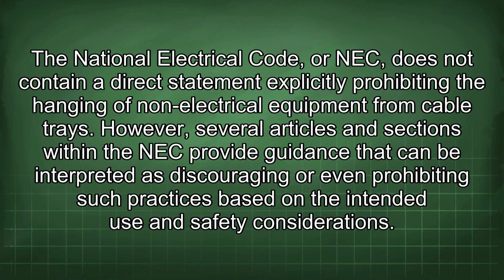The National Electrical Code, or NEC, does not contain a direct statement explicitly prohibiting the hanging of non-electrical equipment from cable trays. However, several articles and sections within the NEC provide guidance that can be interpreted as discouraging or even prohibiting such practices based on the intended use and safety considerations.